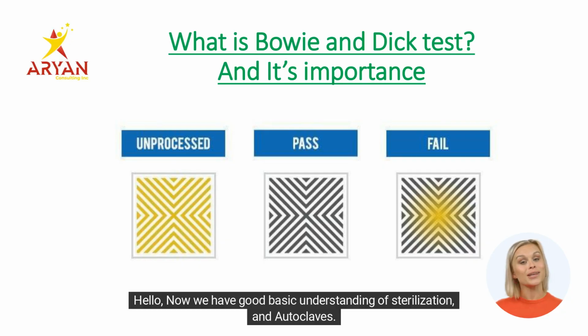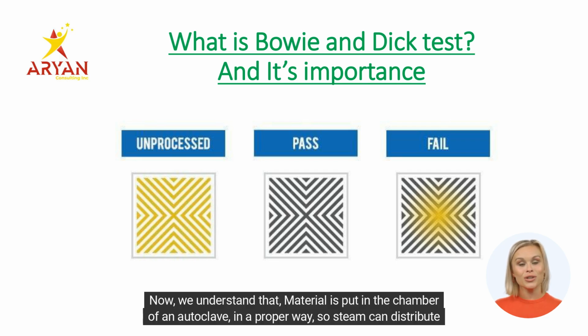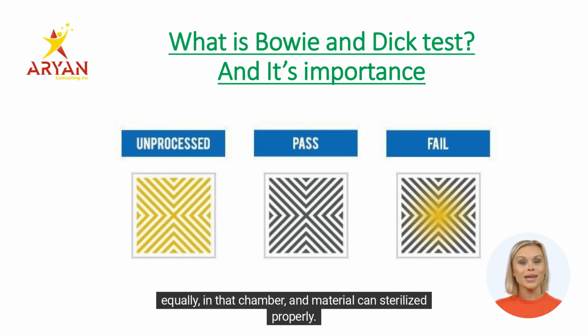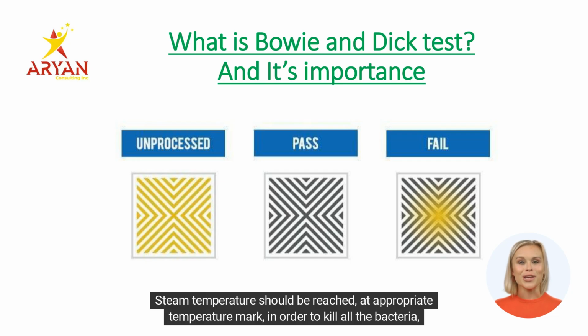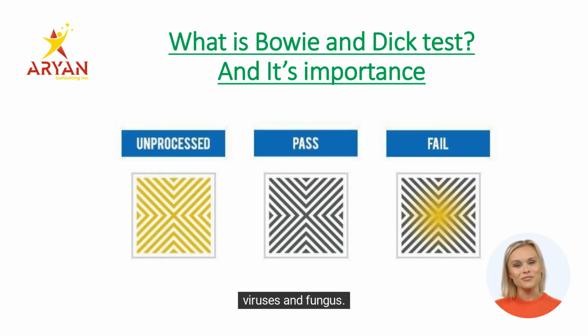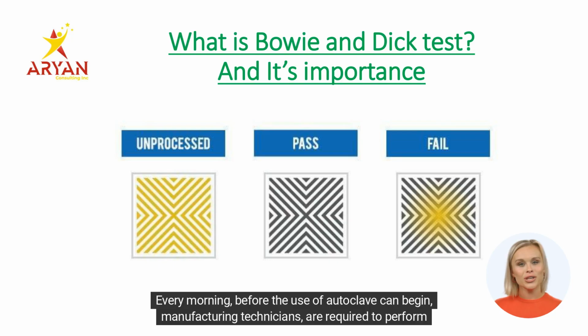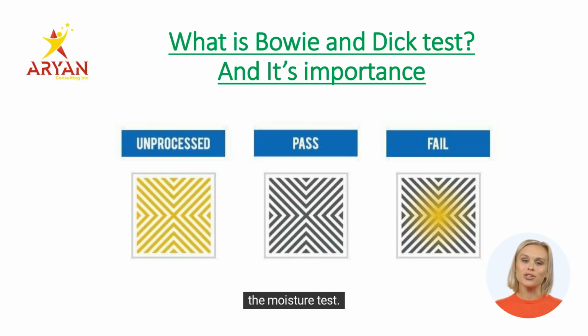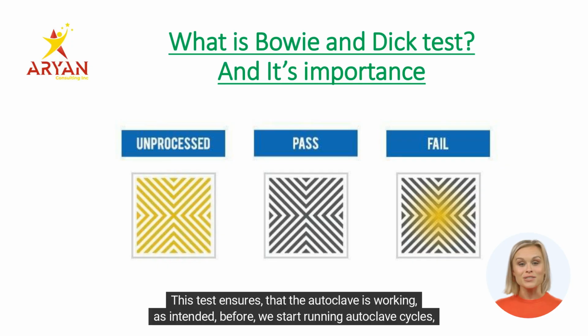Hello, now we have a good basic understanding of sterilization and autoclaves. Now we understand that material is put in the chamber of an autoclave in a proper way, so steam can distribute equally in that chamber and material can be sterilized properly. Steam temperature should reach the appropriate temperature mark in order to kill all the bacteria, viruses, and fungus. Every morning, before the use of the autoclave can begin, manufacturing technicians are required to perform the moisture test. This test ensures that the autoclave is working as intended before we start running autoclave cycles for the day.